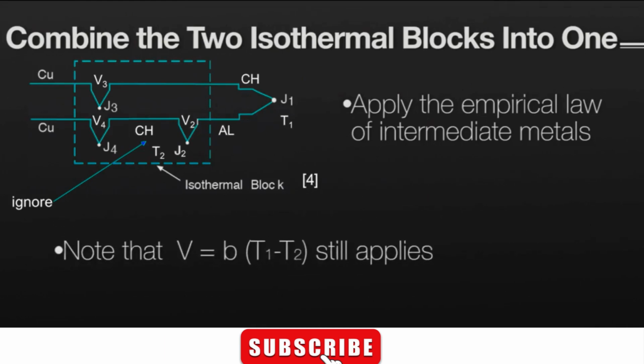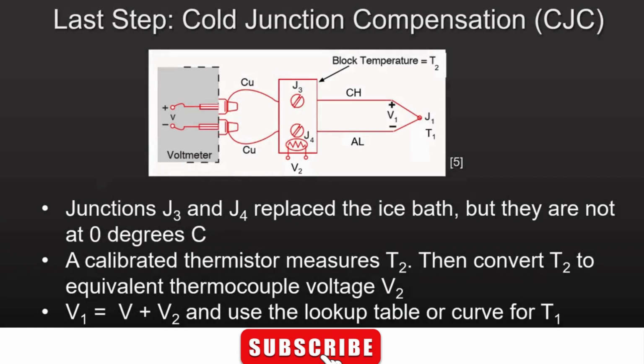Note that the equation V equal to V1 minus V2 still applies, as we haven't introduced any new thermoelectric voltages. This slide shows our simplified system. Now we are going to perform a process step known as cold junction compensation, or CJC for short. We originally substituted our isothermal block of unknown temperature for the ice bath, which had a known temperature of 0 degrees C. Now we need a way to measure the block temperature without using a thermocouple.